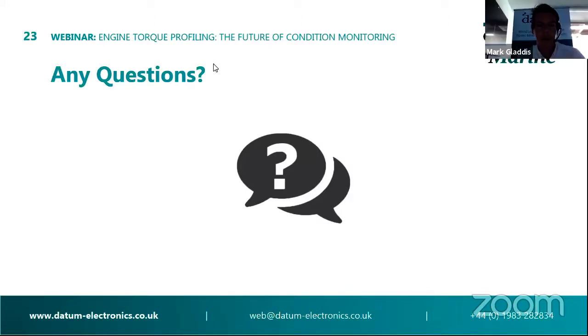Thank you. And the next question, how does the one-time calibration work? Does the system compensate for electronic drift over time? I'll give you a break here, Costas, so I'll take that one. So the nice thing with our system is that directly from the strain gauge, we digitize the signal before it goes to the amplifier. So unlike many other systems in the market where they have analog circuitry at the front end, everything we do from the strain gauge onwards is digitized, which means it's not susceptible to changes in temperature in the engine room. So we do not suffer with drift with our systems. So the day it's installed, it's calibrated, it's zeroed, and that's it for the life of the system.